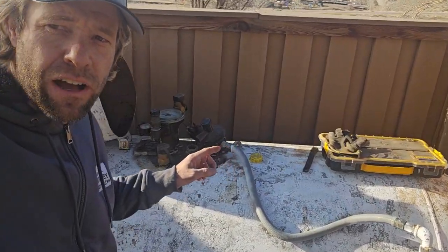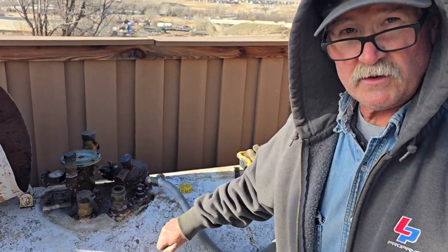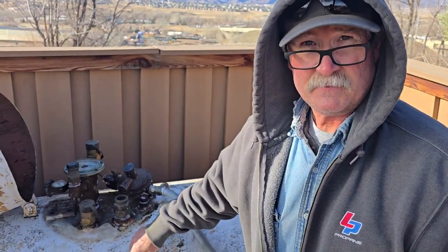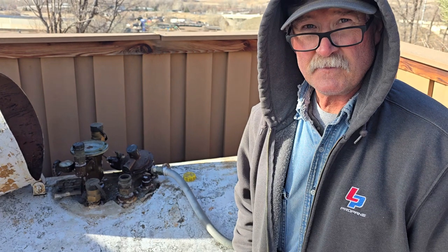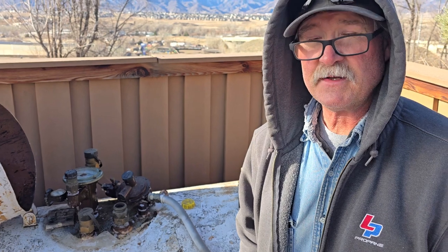Call the company and have them shut it down. Here at the top of a standard propane tank there'll be a main shutoff valve, and a gauge that tells you the content of fluid inside. The tank holds liquid propane, but the appliances use the vapor off of the liquid. So the company delivers a liquid, but we use the vapor — and the vapor is what's extremely flammable.